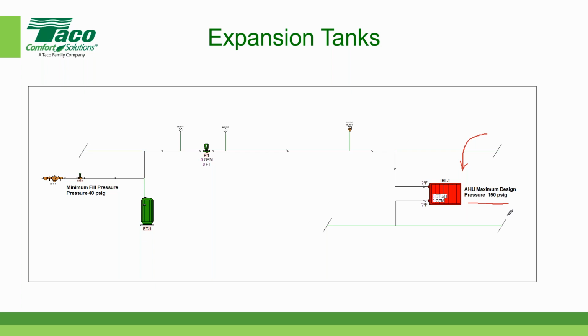So to ensure that this system never gets above 150, we're going to put a safety relief valve in. We're going to set the safety relief valve at 10% below the maximum pressure in this system. Since the pressure maximum wants to be 150, 10% of that is 15. So 150 minus 15 is going to be 135. Isn't that cool? So the maximum pressure at the relief valve wants to be 135.